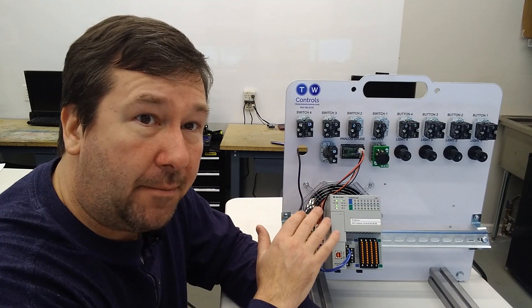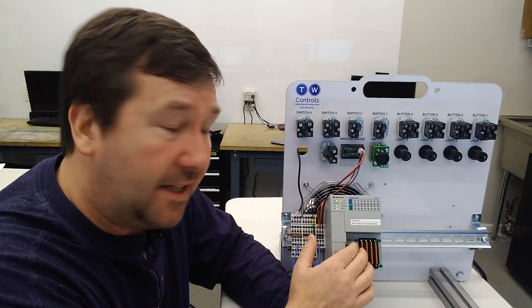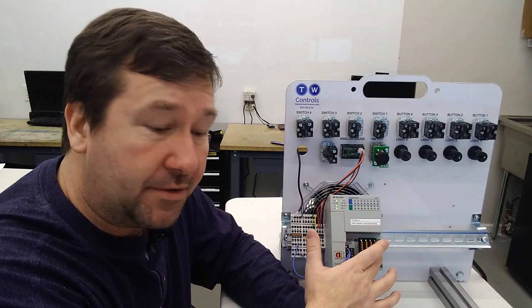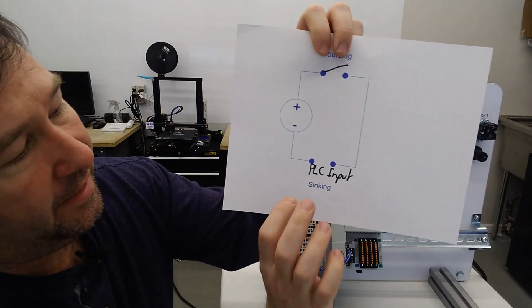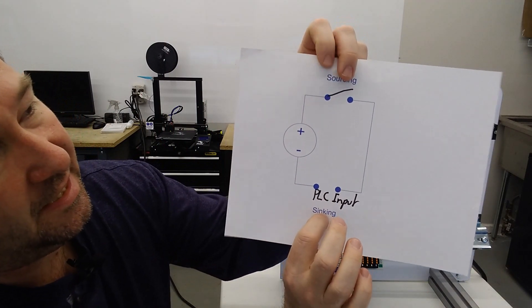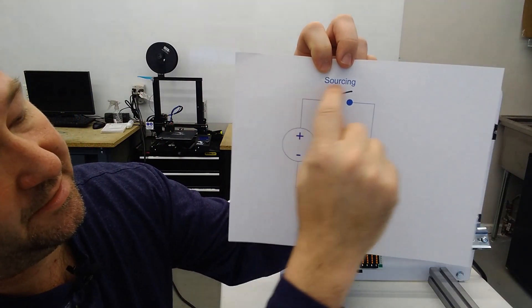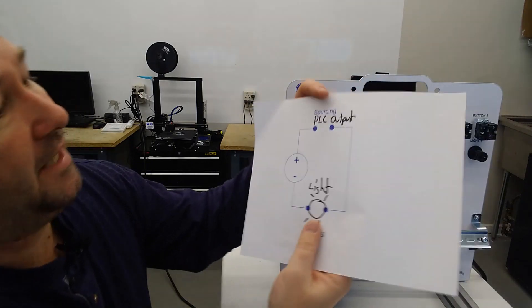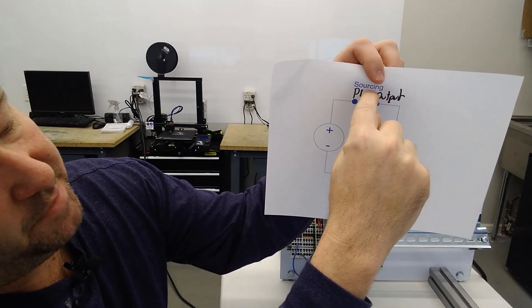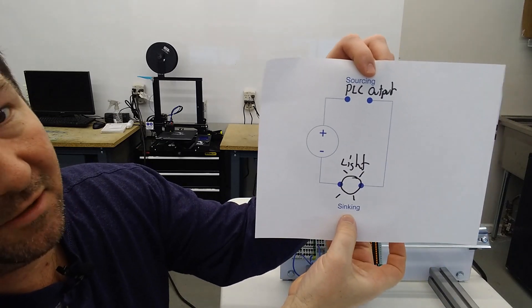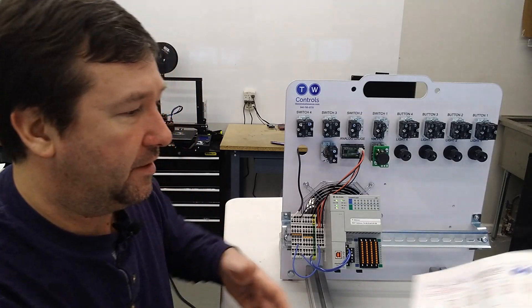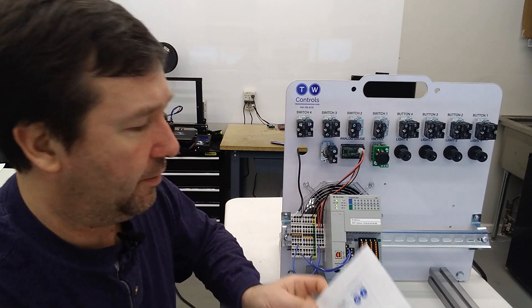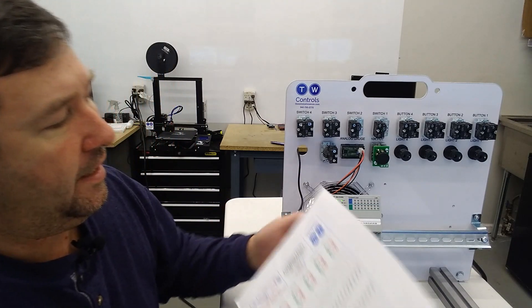In the case of our Compact Logix, its PLC inputs are sinking, and its PLC outputs are sourcing. So we plug in our PLC input down at sinking. That means we'll be using sourcing sensors, and this tells us how we need to wire it. In the case of the PLC outputs, we plug in that we have a sourcing PLC output, and that means our lights need to be wired for sinking.